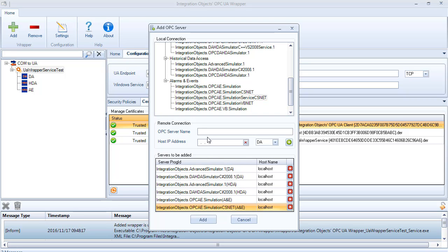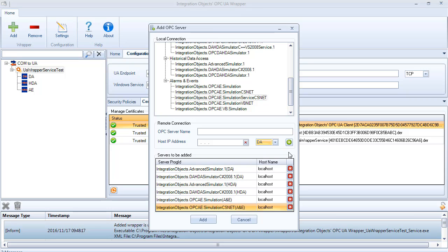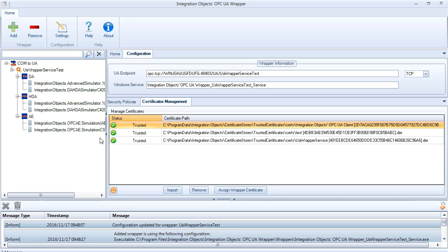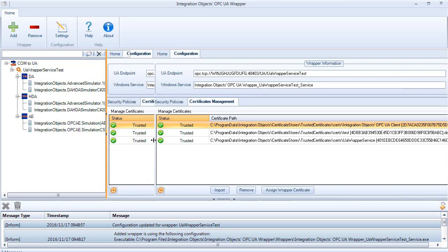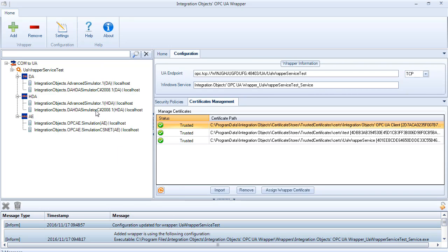You can manually configure a remote OPC server by entering the OPC server name, the IP address of the machine that hosts this OPC server, and the OPC server type: DA, HDA, or A&E server. Click the Add button to confirm your configuration. The servers will be added under the desired wrapper.